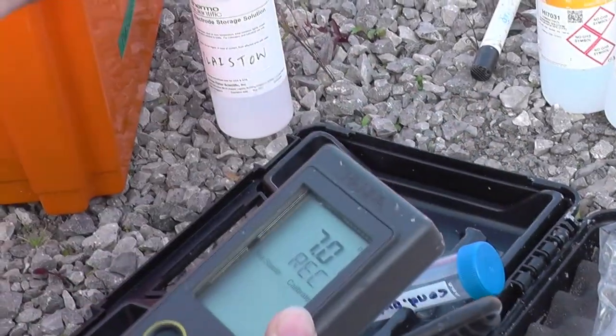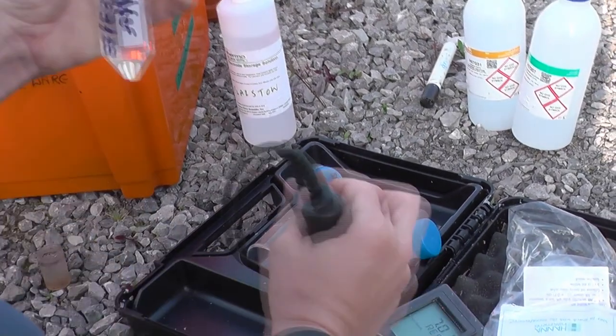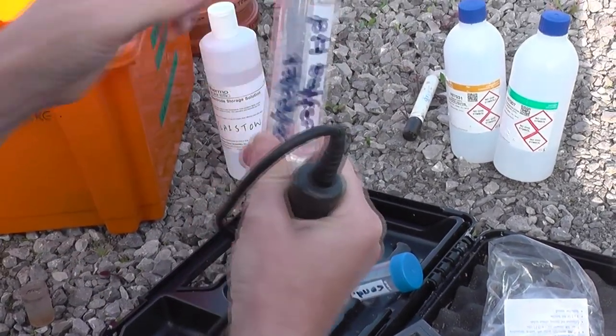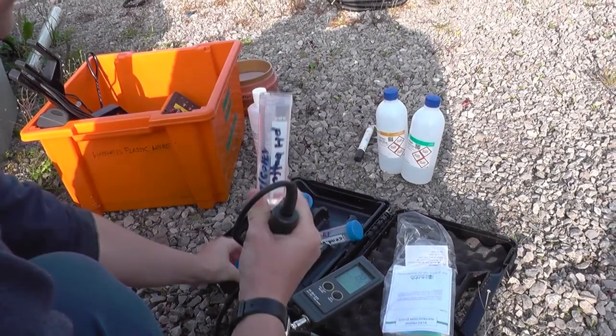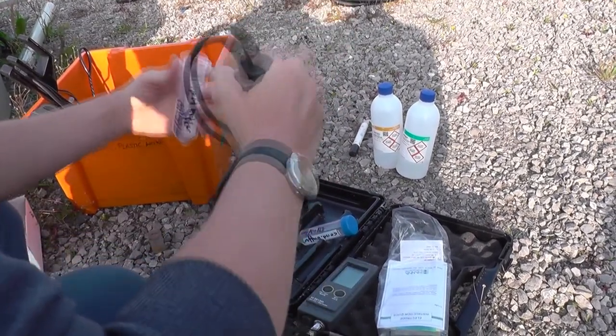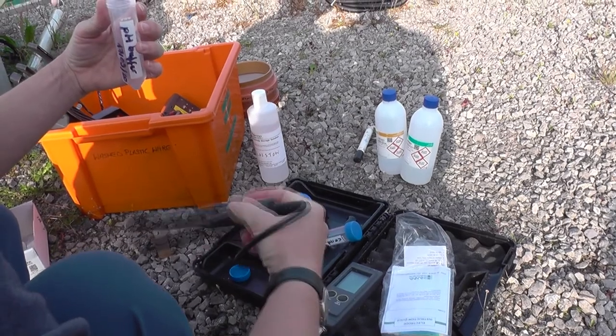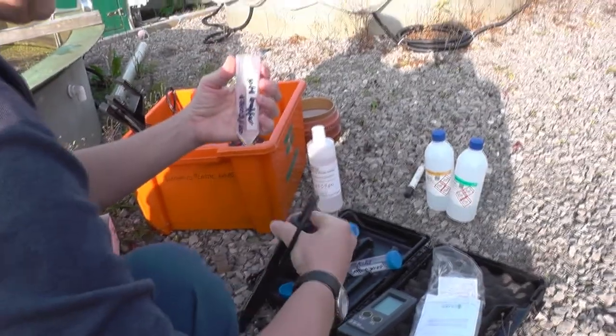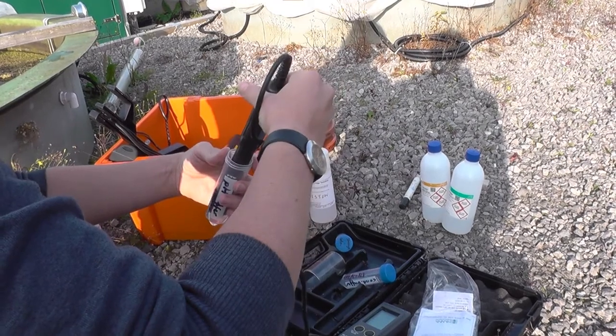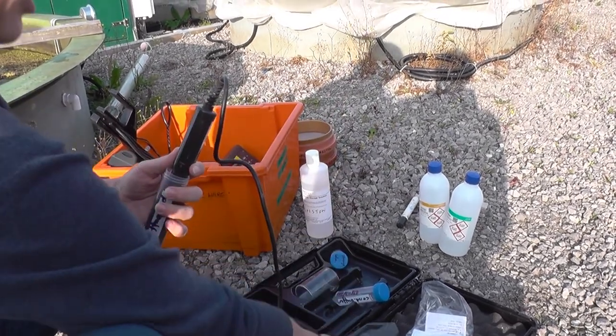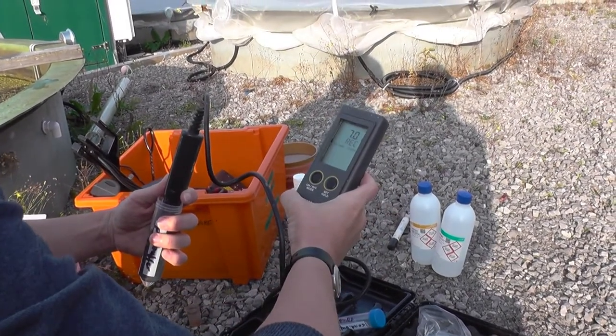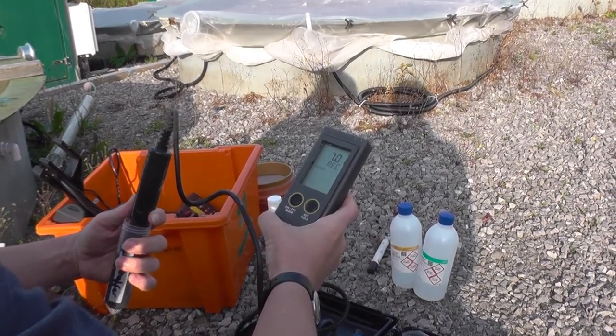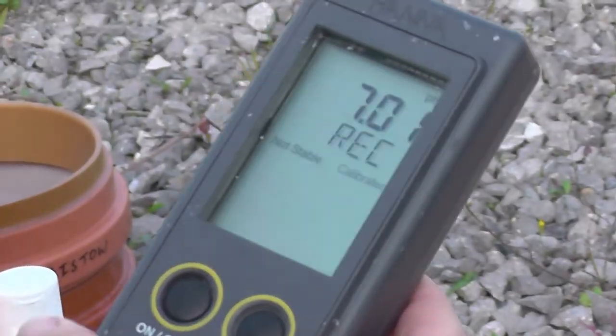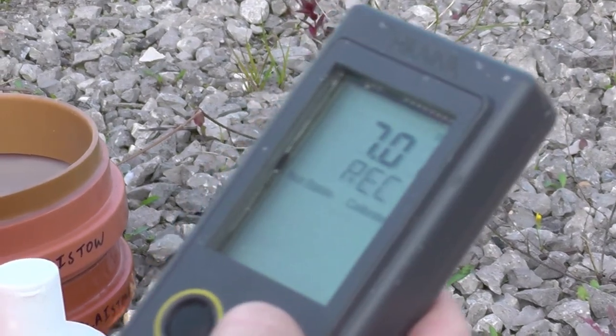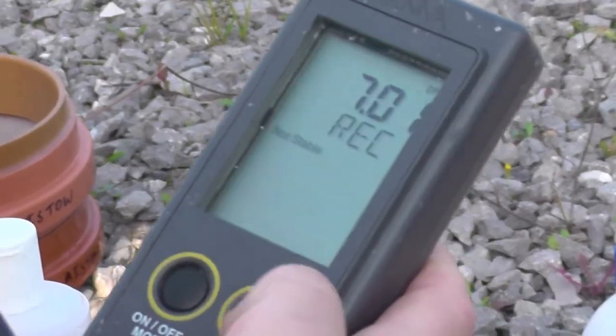So we get our pH buffer, again in a little container, that's easiest to put this probe in, and we can just get a fresh one every so often, maybe every half year or so. So try and shake off any remaining RO water to not mess up the pH of this. Stick it in, and then this tells us it's recording. It's not stable yet. It can be a bit fickle sometimes, so we want for this to become stable. It says calibrated now. So we press set.